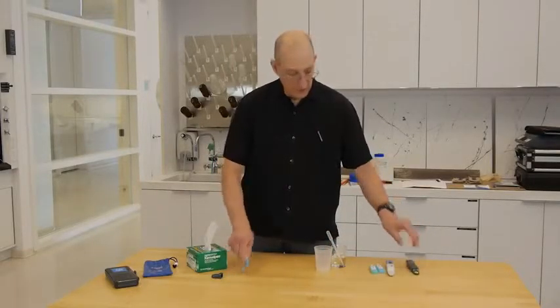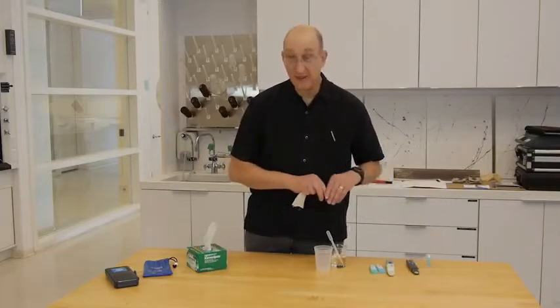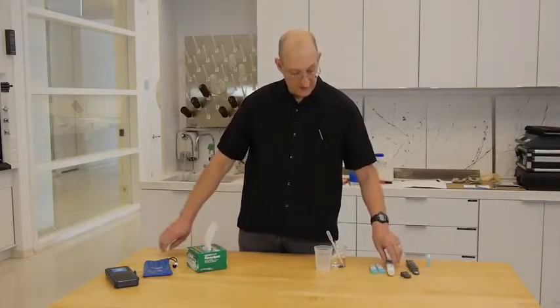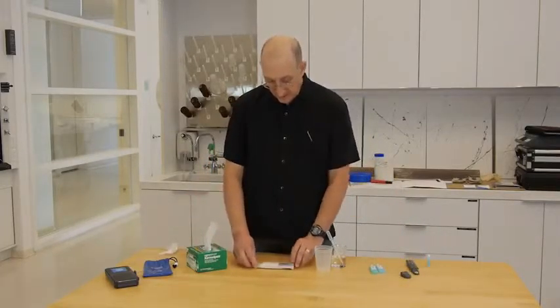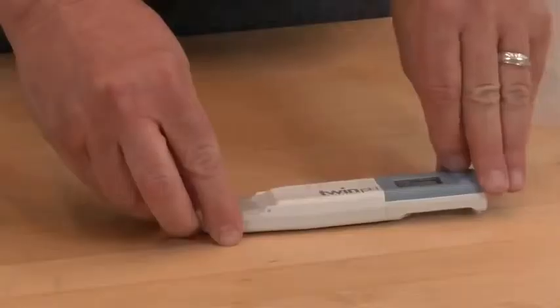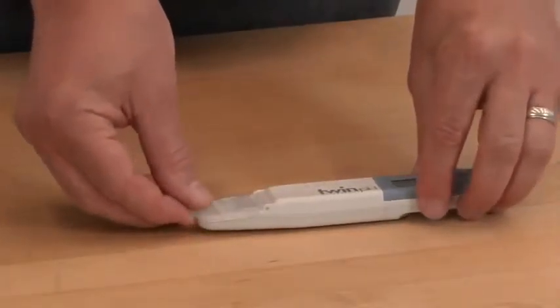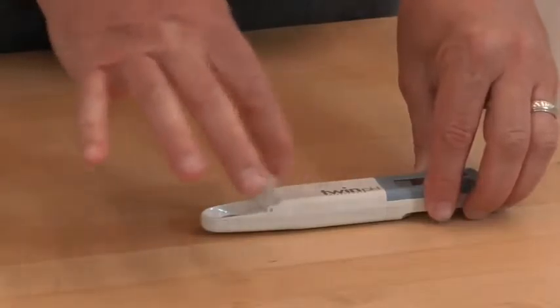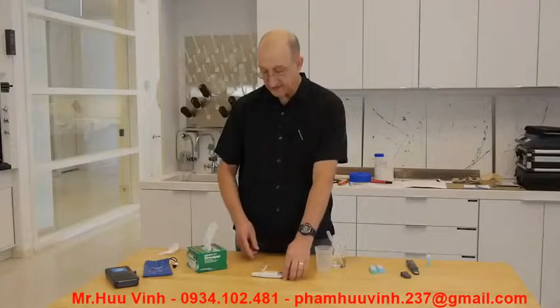For the pH meter, it's more or less the same process, except we're going to calibrate to 2 points. Again, we turn the meter on, and we open the sample well. If you prefer, you can take this little flap off. I like to leave it on to protect the electrode.